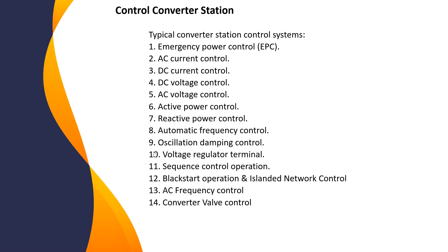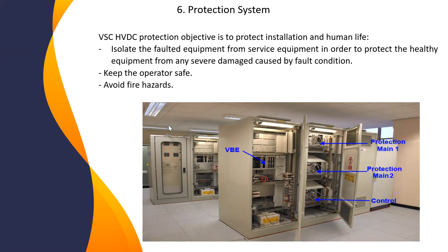And then the last topic, we are talking about protection here. What is protection? Protection is actually to protect installation, to isolate faulty equipment, and then to protect the healthy equipment in order not to be damaged when caused by fault. When we are talking about protection, we are also talking about human life. The aim is also to keep operators safe and to avoid fire hazard in substation. So this is an example of control and protection cubicle, we have protection main 1, protection main 2, control, and then this is to control a valve here.